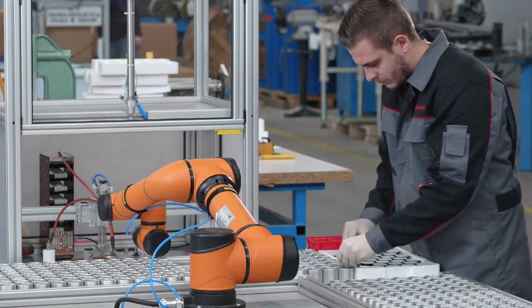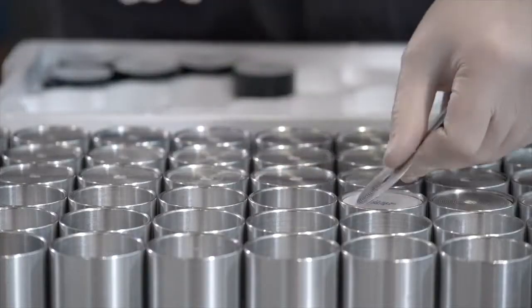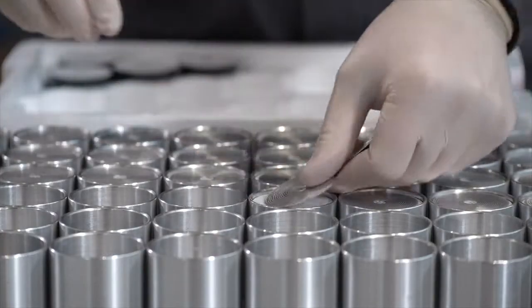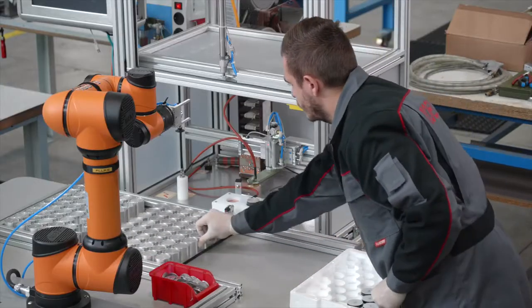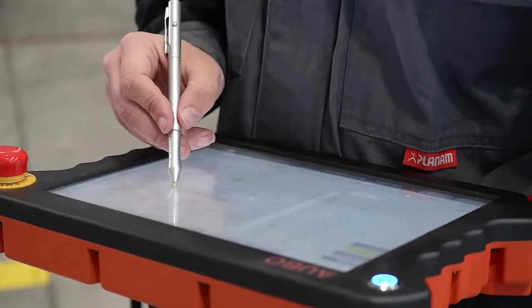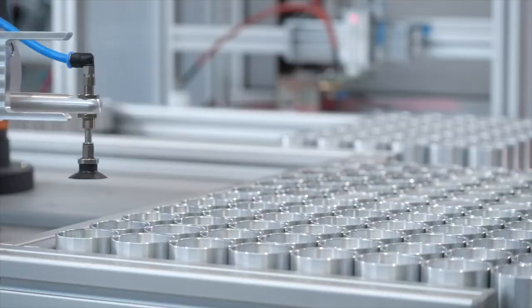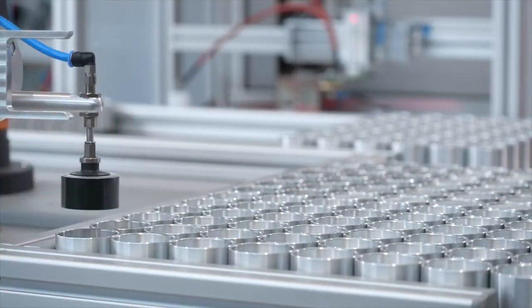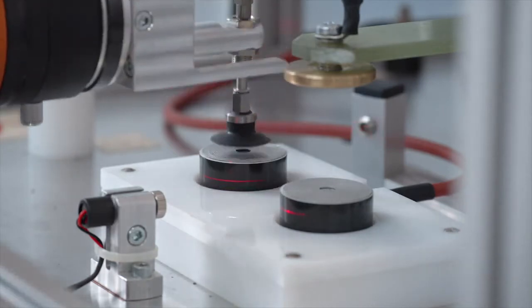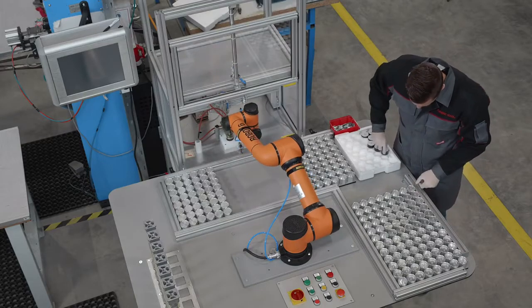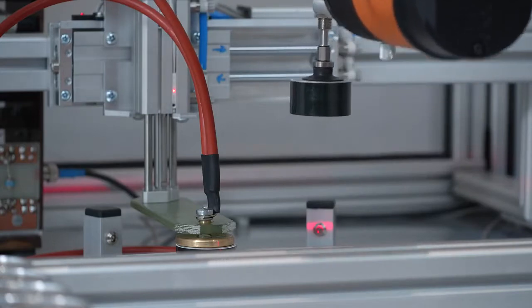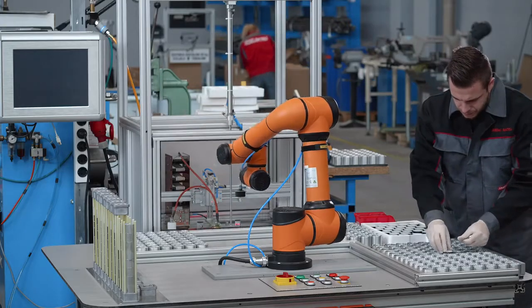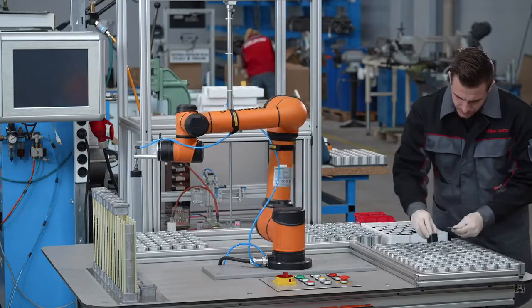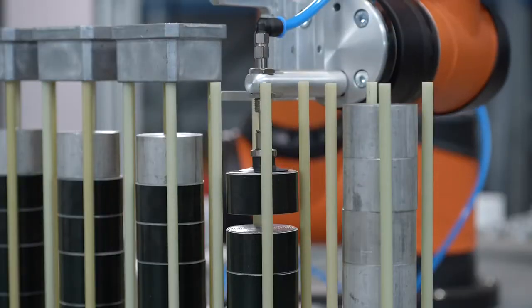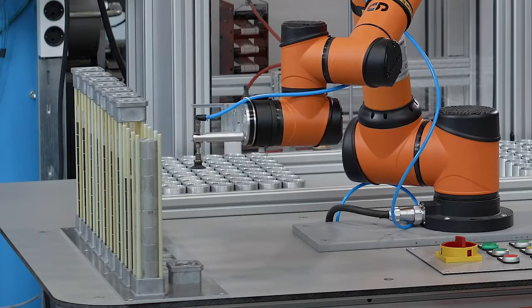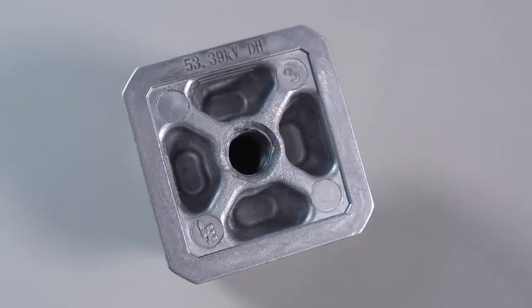The main components of DH class surge arresters are its varistors, which we purchase at professional and verified producers. On a specialized testing machine, we test the residual voltage of each varistor. Based on the values of the residual voltage of each varistor, we robotically assemble the core with the help of a special algorithm. The combined residual voltage of each surge arrestor core is engraved with a laser on the bottom fitting.